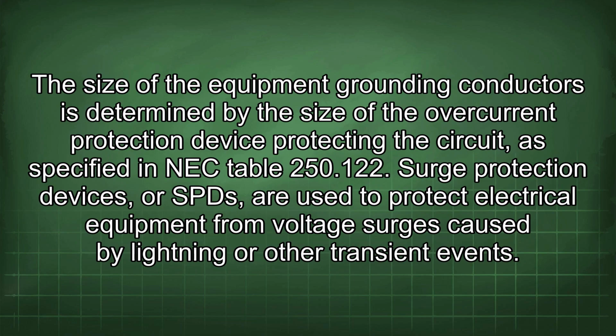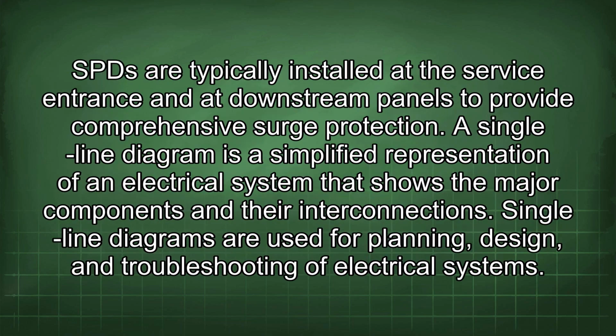Equipment grounding conductors are used to connect the non-current carrying metal parts of equipment to the grounding system. The size of the equipment grounding conductors is determined by the size of the overcurrent protection device protecting the circuit, as specified in NEC Table 250.122. Surge protection devices, or SPDs, are used to protect electrical equipment from voltage surges caused by lightning or other transient events. SPDs are typically installed at the service entrance and at downstream panels to provide comprehensive surge protection.